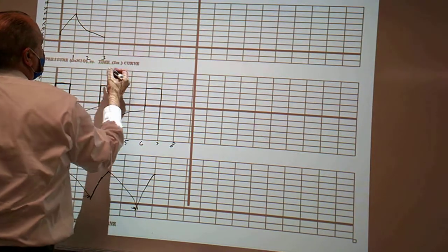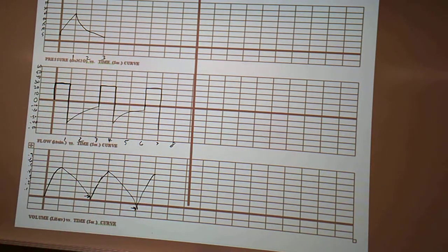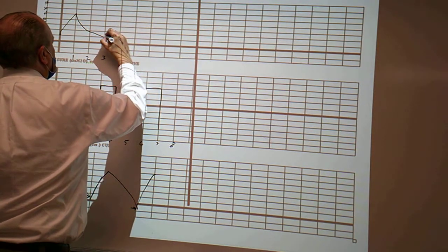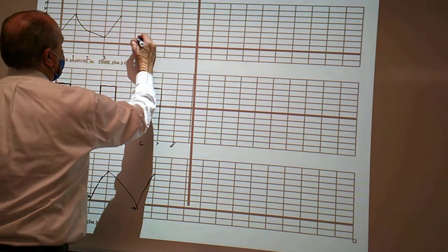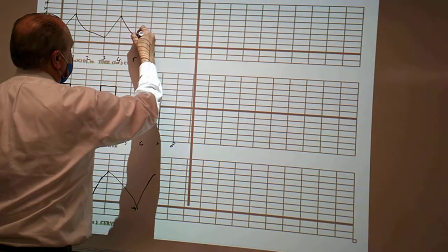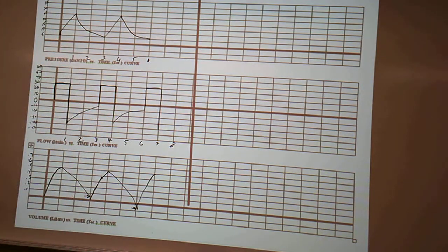So do you do anything here because there's air trapping? Yes, that pressure tracing needs to come back to baseline at the point where the next breath starts. You're going to go back to 5. So there's no pause in between. Correct. There's no pause. Once flow is stopped, right away at that point the pressure should be 0 or baseline.